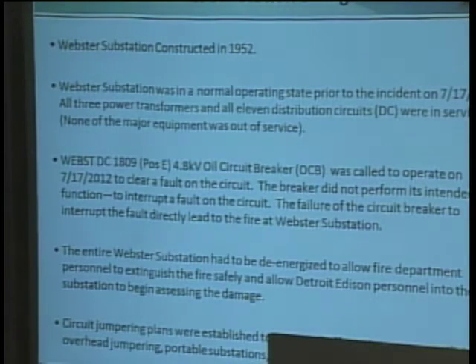Webster Substation this summer was operating normally, and all three power transformers and 11 distribution circuits were in service. One of the problems was that Webster 1809, a 4,800 volt circuit breaker, was called to operate on 7/17 to clear a fault on the circuit. The breaker did not perform its intended function, and that failure of the circuit breaker to interrupt the fault directly led to the fire at the substation.